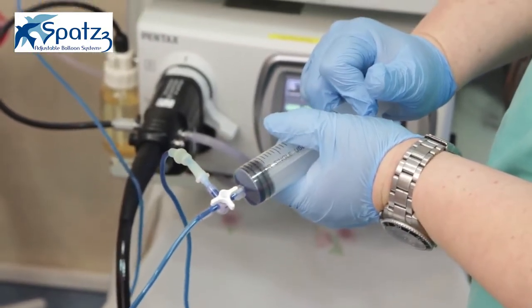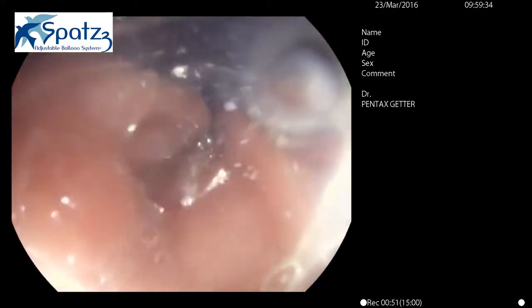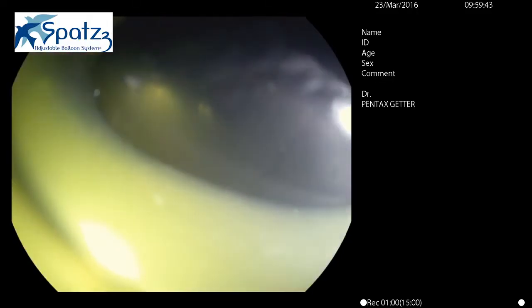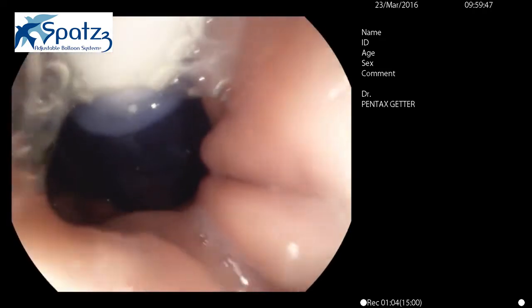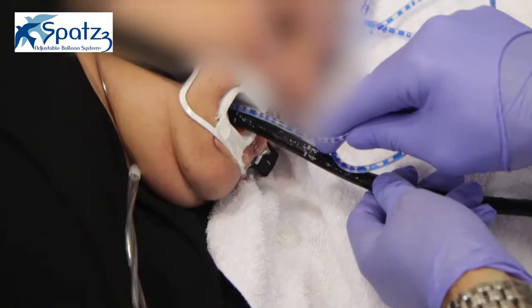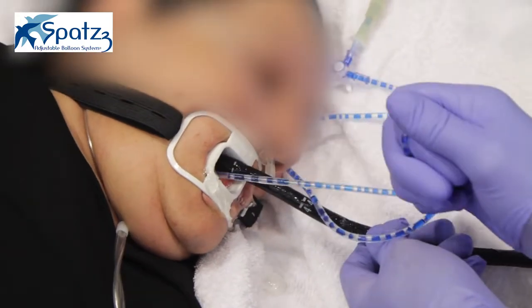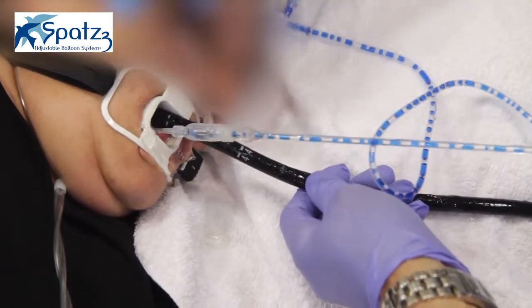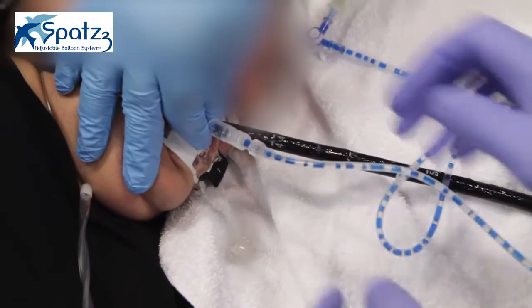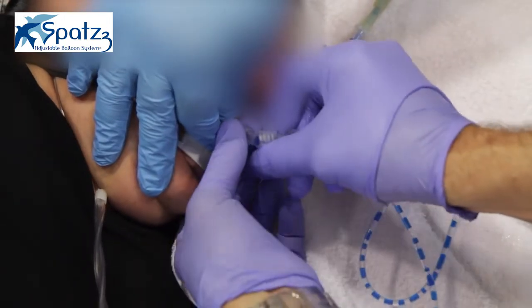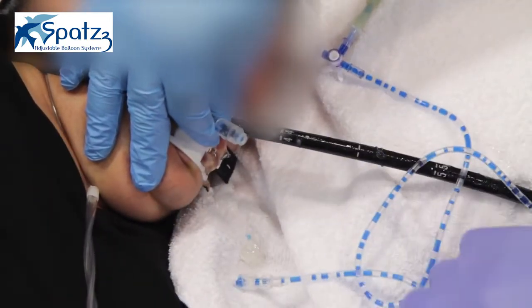Once inflation has concluded, withdraw the endoscope to the distal esophagus. As you pull back, you will see the balloon and you will feel pressure as the balloon releases from the insertion facilitator. While the endoscope remains in the esophagus, pull the extension tube until the valve exits the mouth. Secure the valve. Disconnect the extension tube.